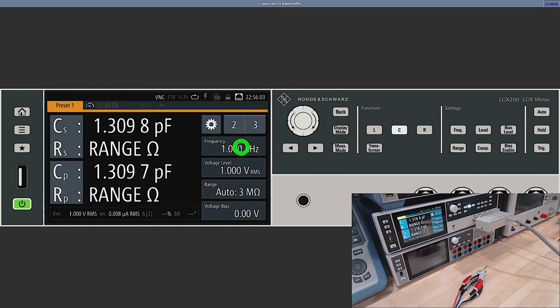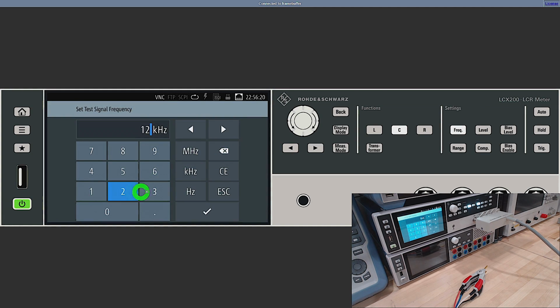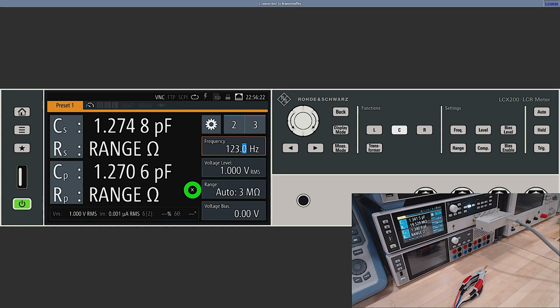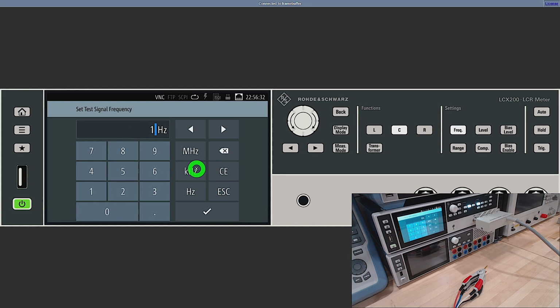The frequency is set to 1 kilohertz. Now in this instrument, you can set the frequency from 4 Hz all the way to 10 megahertz, which is a fairly broad range. It means that you can measure all kinds of different passives across a variety of self-resonance frequencies. And the frequencies are not quantized. You can set them to anything you want. So for example, I can set it to 123 Hz, and you should have no problem with that. And this is because we saw internally the architecture was using these DACs and modulators and demodulators, allowing you complete freedom to set the frequency like you would in a synthesizer. So let's go ahead and put this back to 1 kilohertz where we want it.